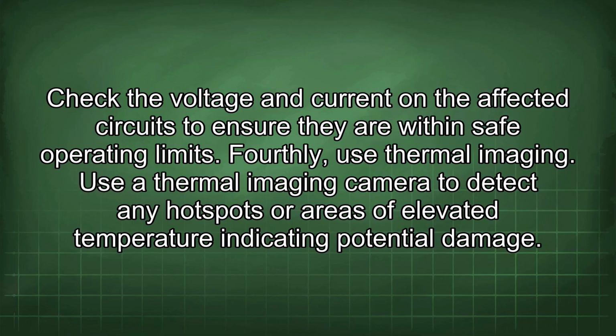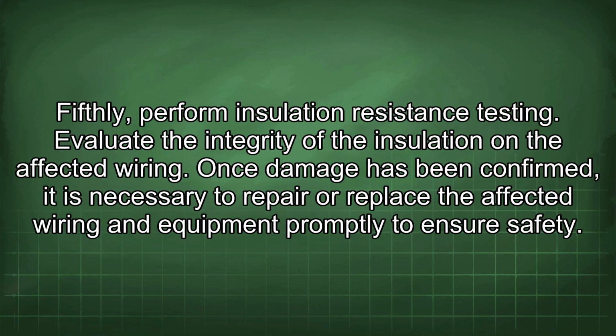Fourthly, use thermal imaging. Use a thermal imaging camera to detect any hotspots or areas of elevated temperature indicating potential damage. Fifthly, perform insulation resistance testing. Evaluate the integrity of the insulation on the affected wiring. Once damage has been confirmed, it is necessary to repair or replace the affected wiring and equipment promptly to ensure safety.